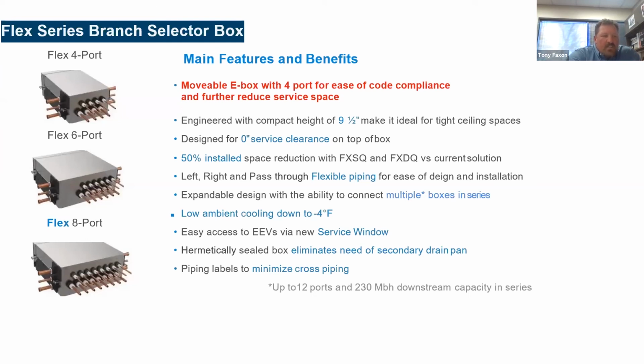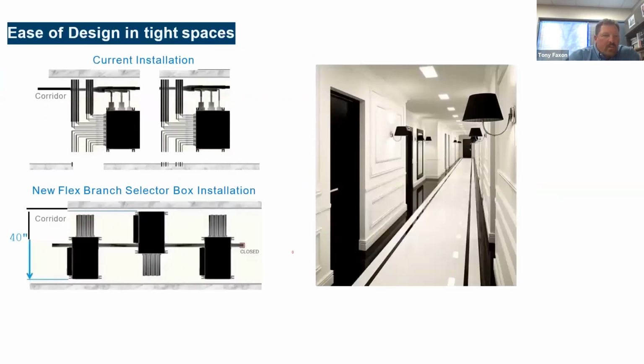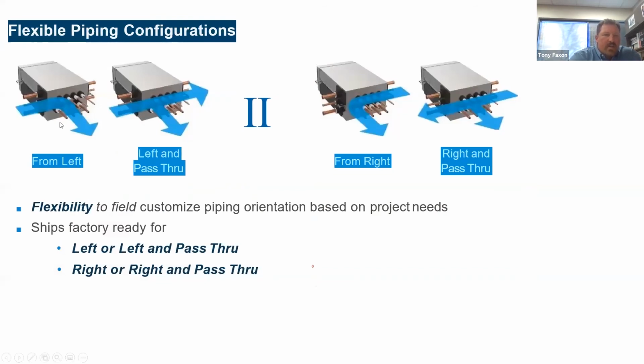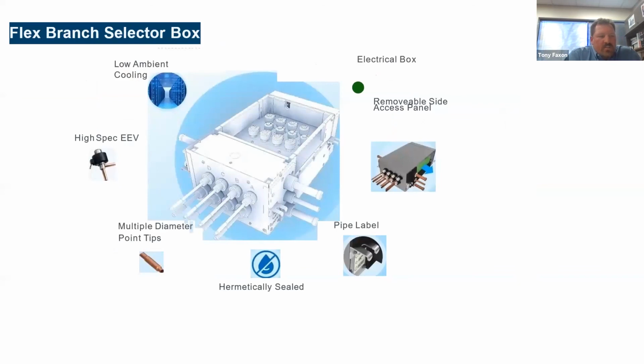The main new feature of these boxes is the pass-through piping. Instead of having to wire off of a piping main to each box, as you can see here, and having to have a wide hallway, you simply install them in series like you see here. They can pass through from either side. They can pass through left and through, from right and pass through. So direction is not a factor when installing these. The reason the service clearance on top is no longer required is due to a service window that's designed on 3 sides of the boxes that you can see right here, and back here, so that you can get into the box to service the motor heads.